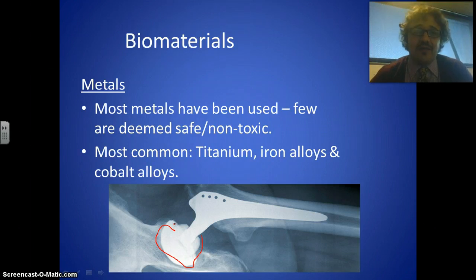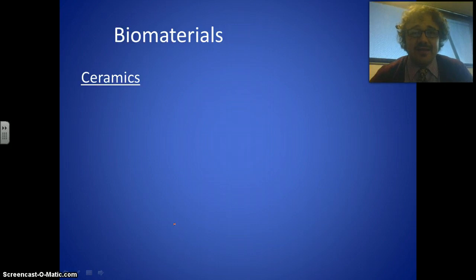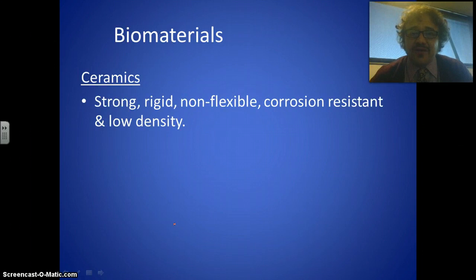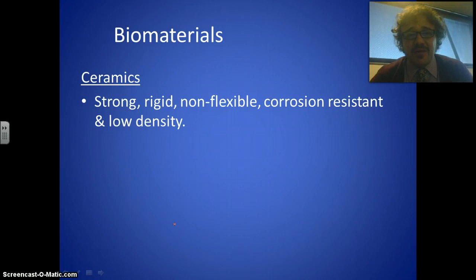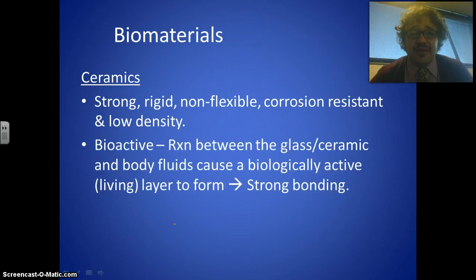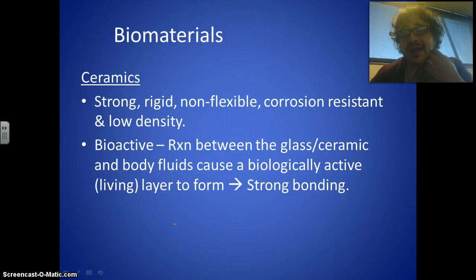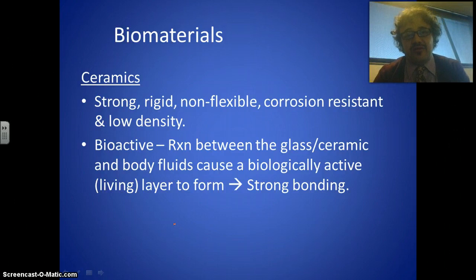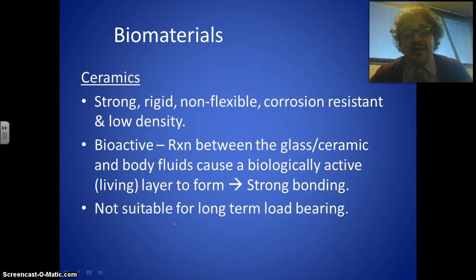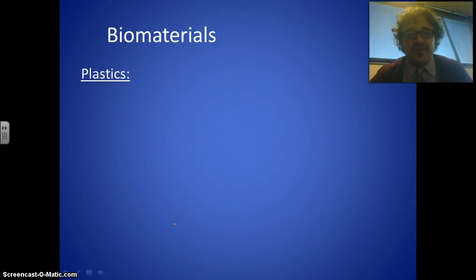Ceramics — like your glasses, plates, and cups — are also used. They tend to be strong but rigid and non-flexible. They don't rust, so they're corrosion resistant, and they're very low density, making them fairly light compared to metals. They're called bioactive, meaning there's a reaction between the ceramic and body fluids that causes a living layer to form between the ceramic and surrounding bone — creating a particularly strong bond. However, they're not suitable for long-term load bearing, so you wouldn't use them on your femur, which deals with a lot of stress.